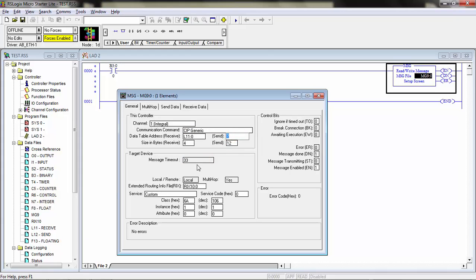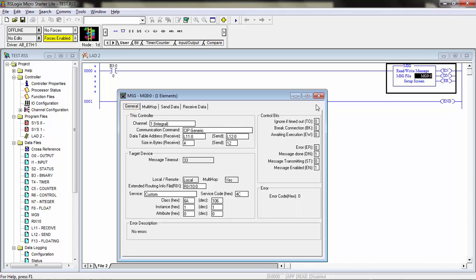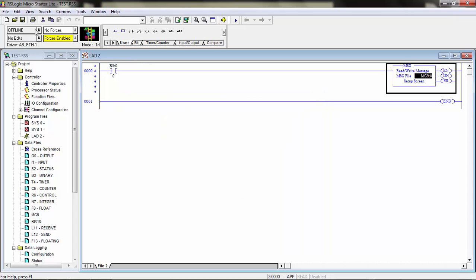The send information will go from L12, which has already been set up as 32-bit locations. The service code for command control is 4C, so we'll go ahead and enter that in. Everything else is already set up — the multi-hop tab has the IP address of the CVX controller already configured, which is where the message will be sent to. We'll go ahead and download this to the PLC now and test it out.